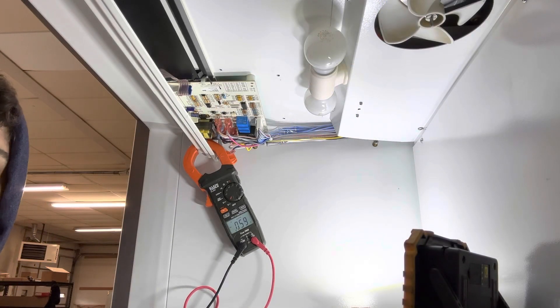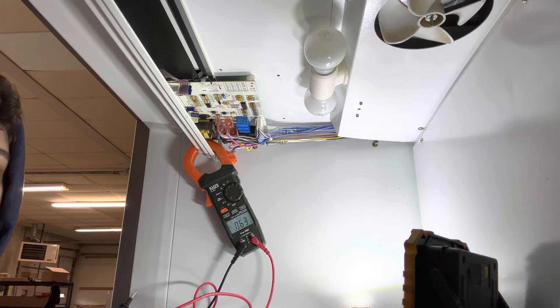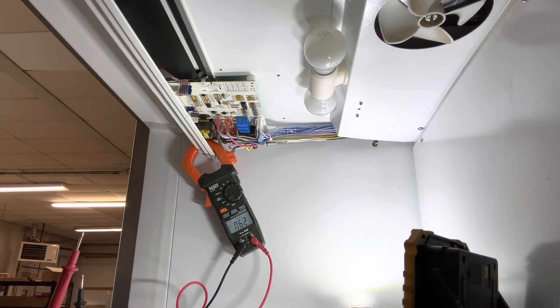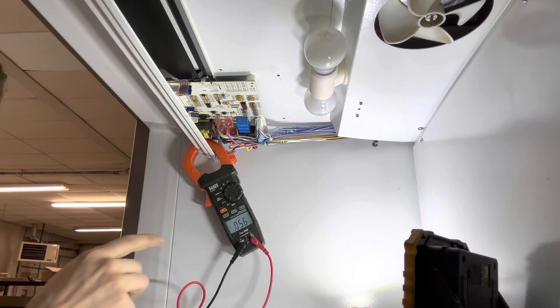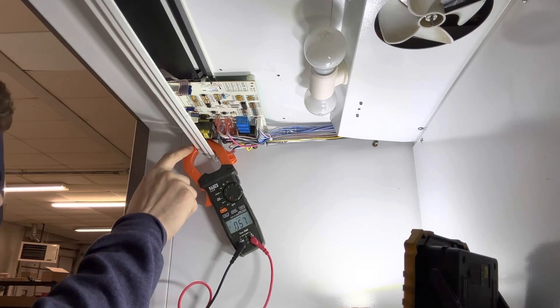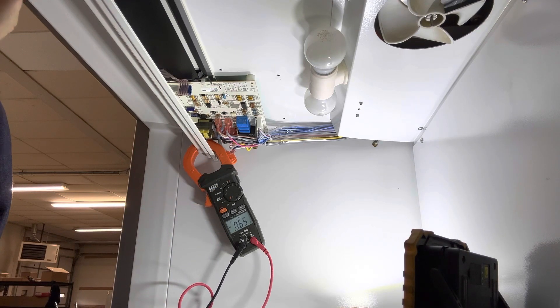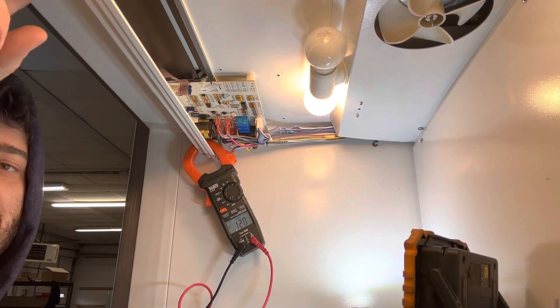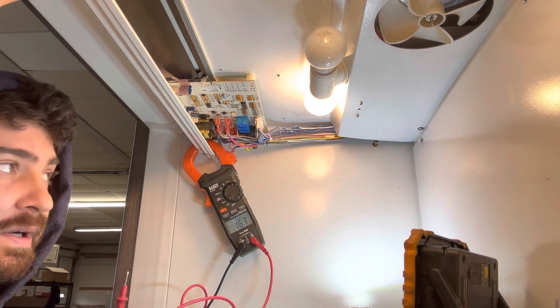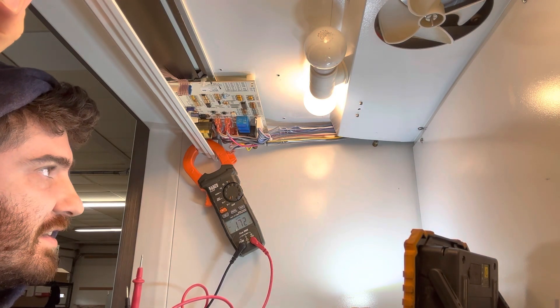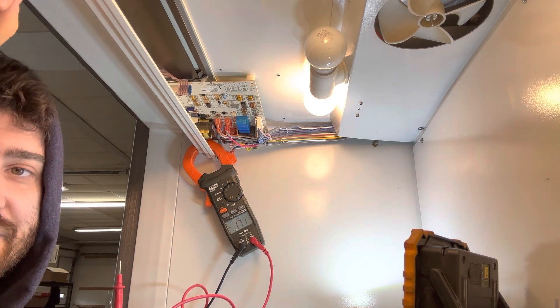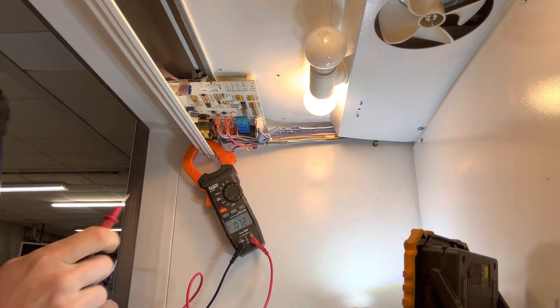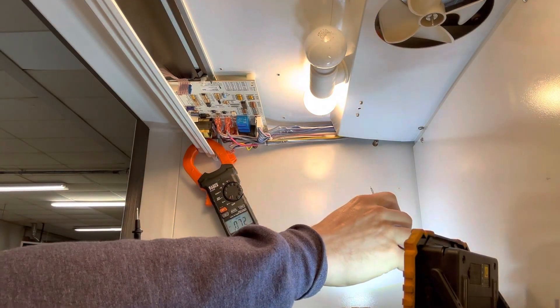So what we're going to do now is restore power to the unit and throw it into defrost, and we're going to take a meter reading on the control board. I use an amp meter, so don't be thrown off by me clamping this to the ceiling. It's just so you guys can see. Let's turn it on. I hear the compressors go on. I'm going to hold that ice button for about 15 seconds, and when I do that and this thing goes into defrost like it just did, that control board should be shooting 120 volts off of the defrost terminal. Now I'm going to ground to a screw in here, maybe up here in the middle of the unit, just to be out of the way so you can see.